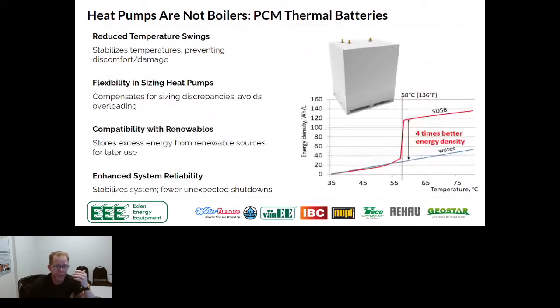So the other thing to keep in mind that's really interesting that's coming into play, and I wanted to share this slide, is that we're seeing really cool new technology coming into the market where we're moving away from buffer tanks and we're now starting to see thermal storage batteries, specifically phase change material. So the idea behind this is this phase change battery would be about the same size as the chair you see behind me, but it's the equivalent to 300 liters of water. So it has 4 times the energy density of a storage tank.